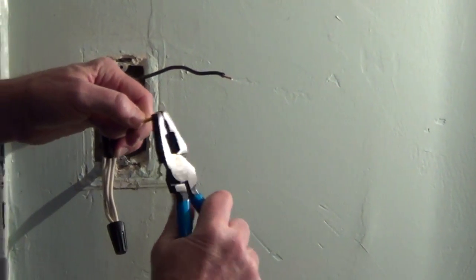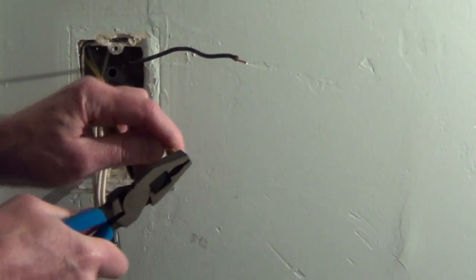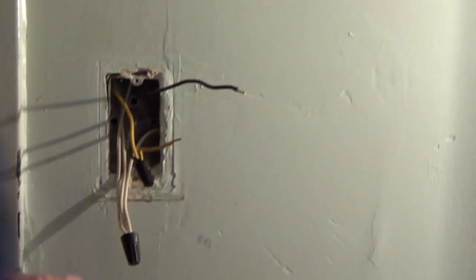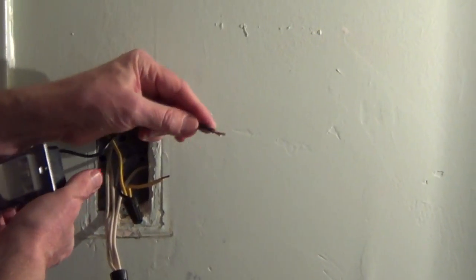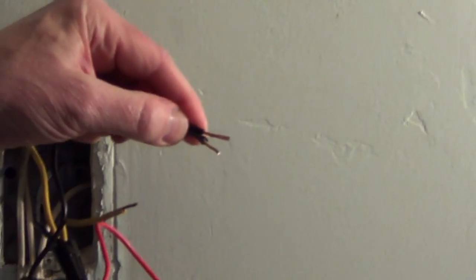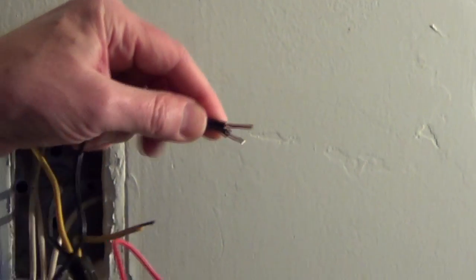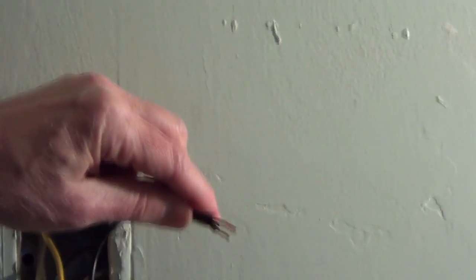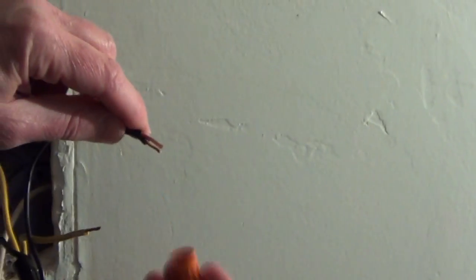The dimmer switch came with wire connectors and now we're going to attach the wire from the service panel to this black wire. Whenever you're connecting solid wire to stranded wire I like to have the stranded wire about an eighth of an inch longer than the solid wire.